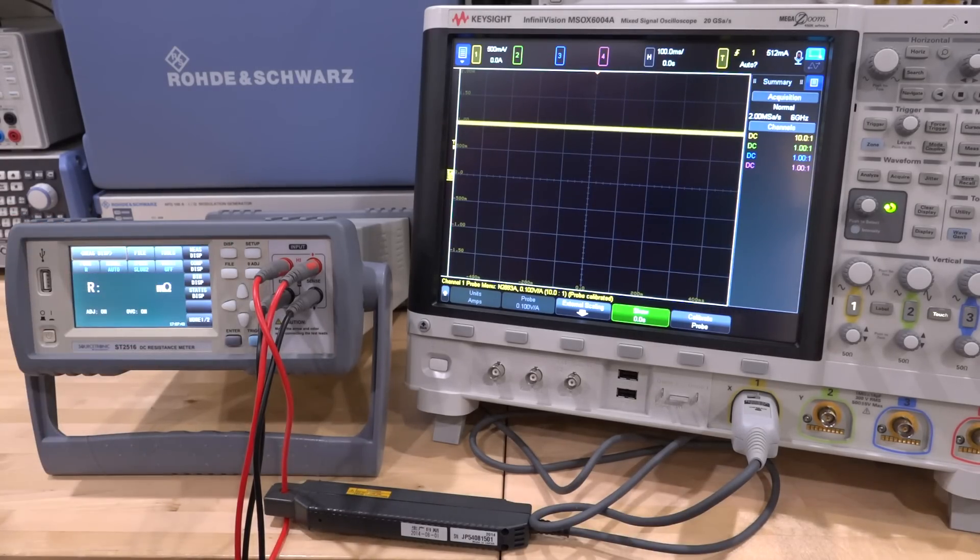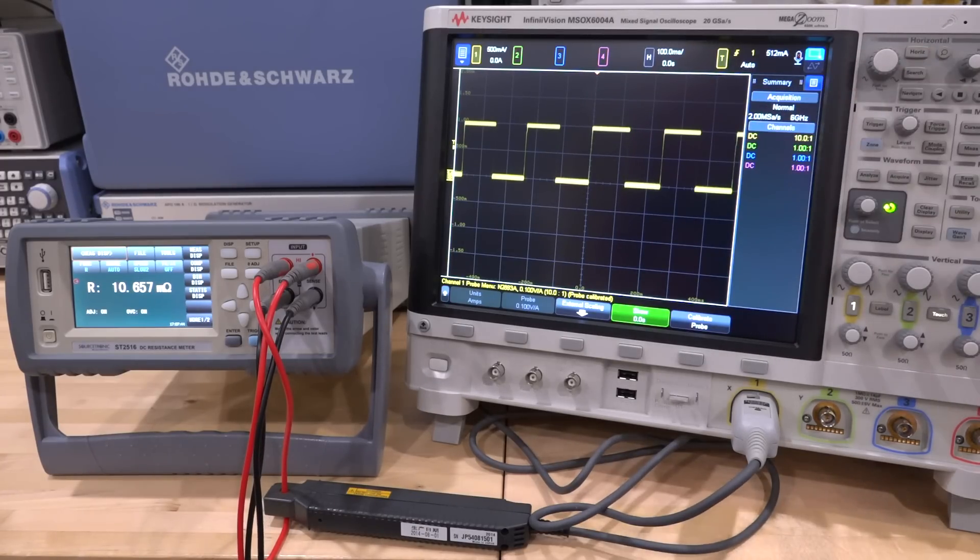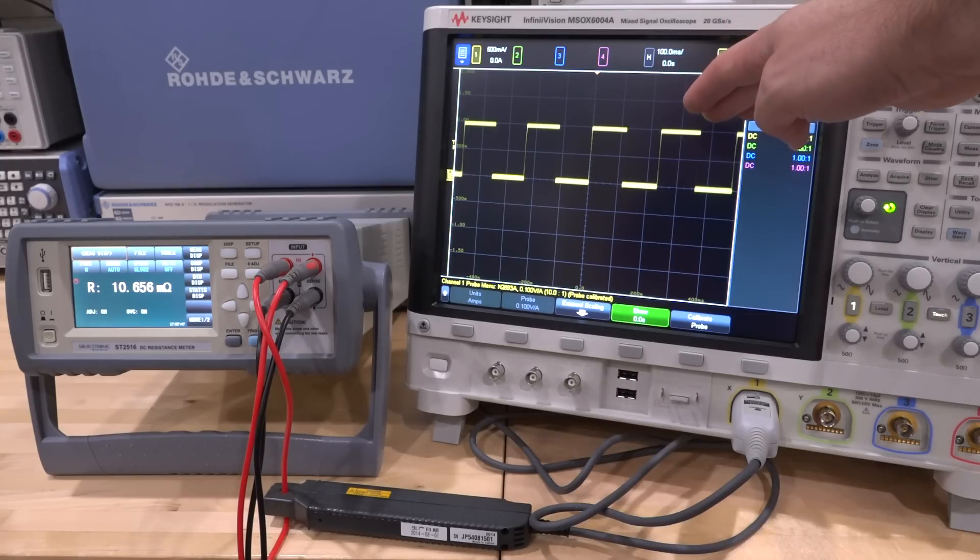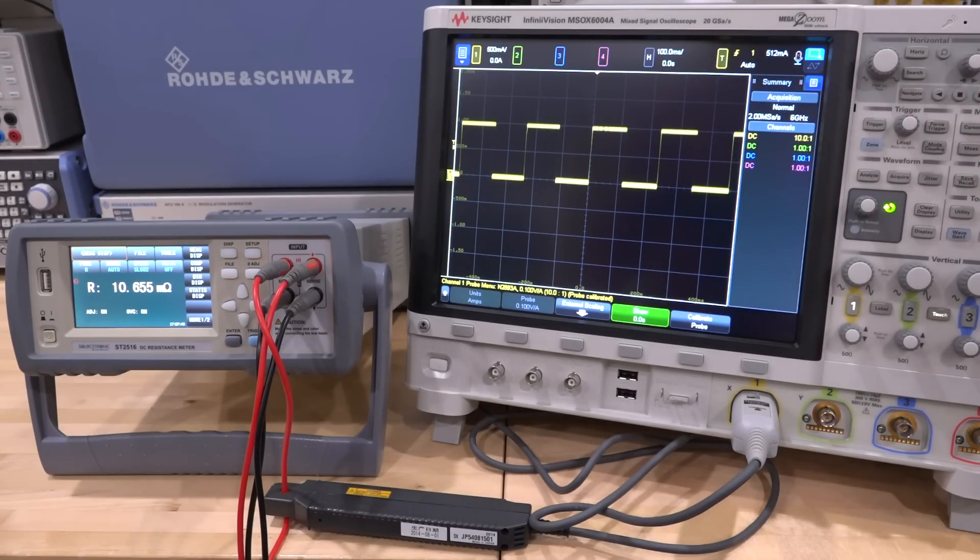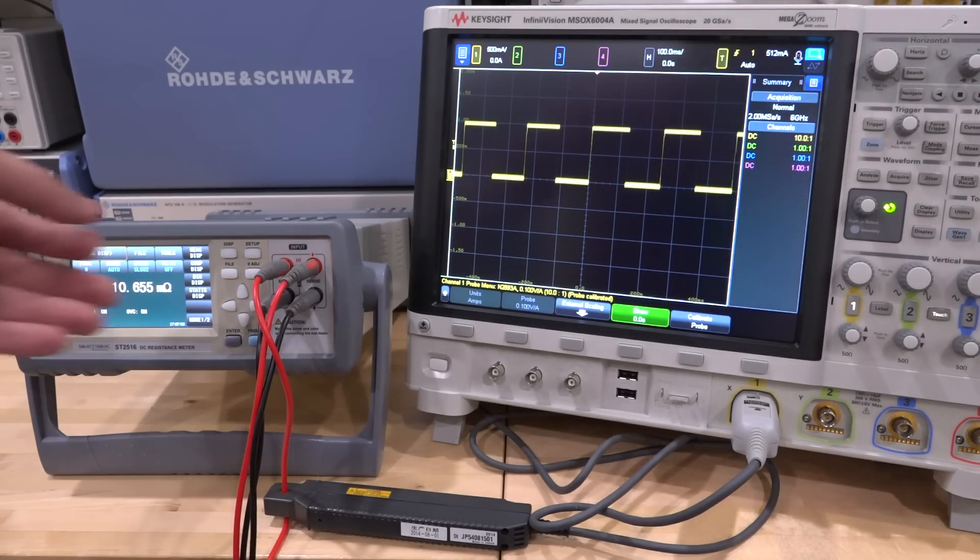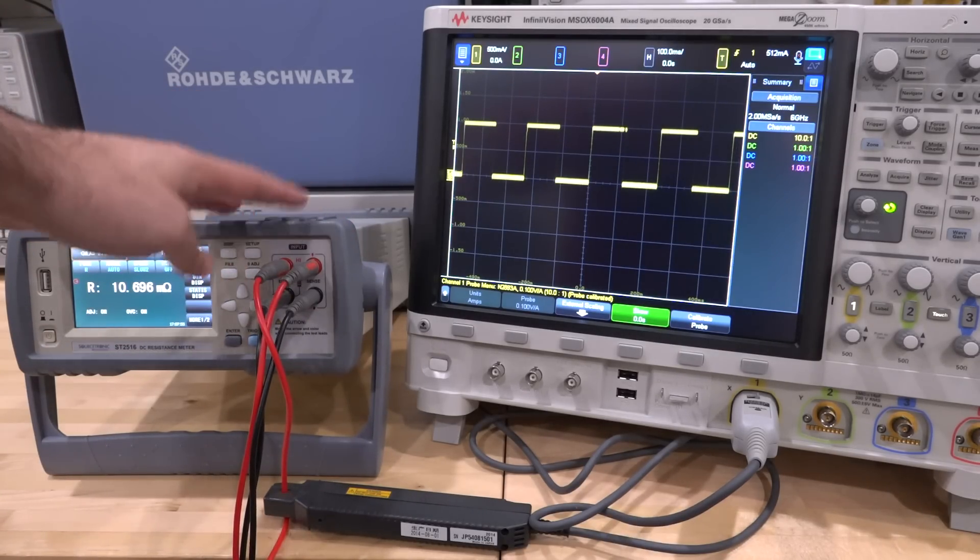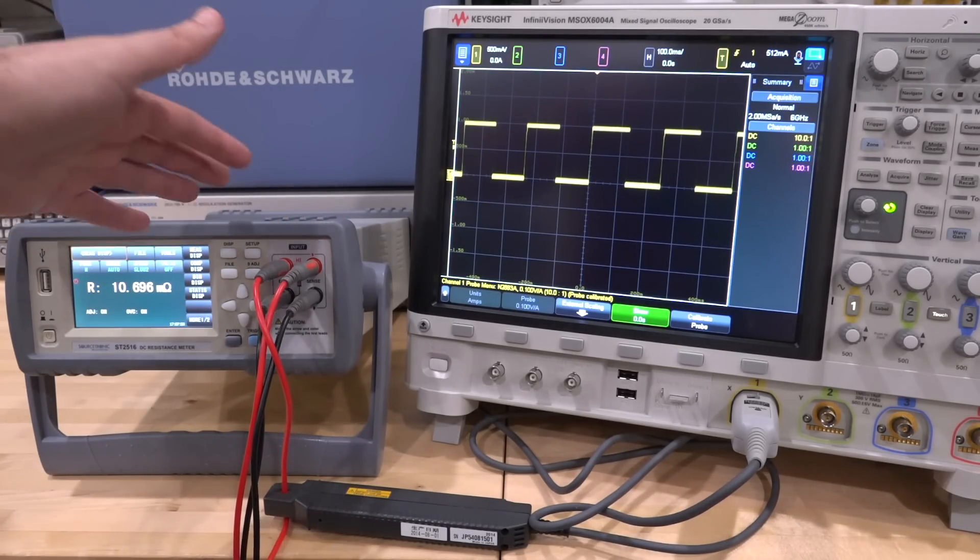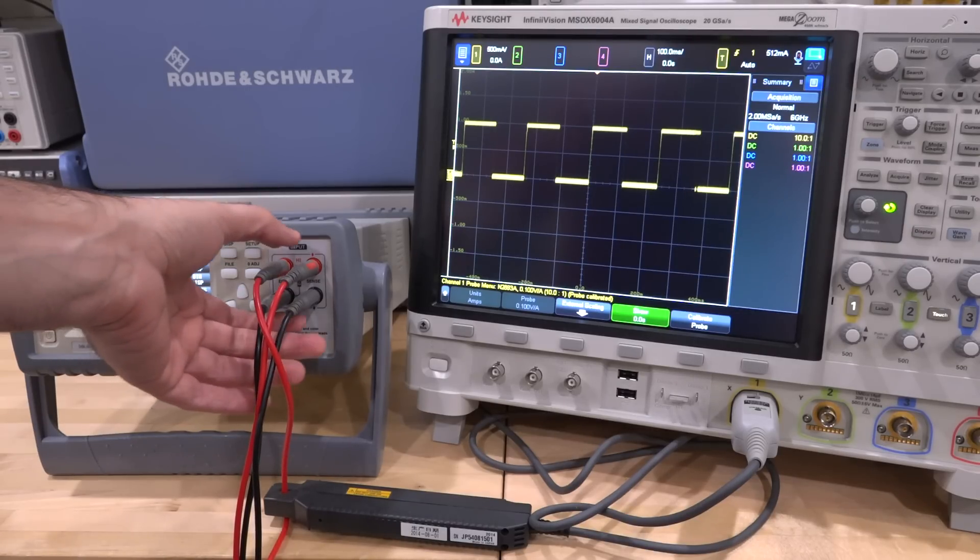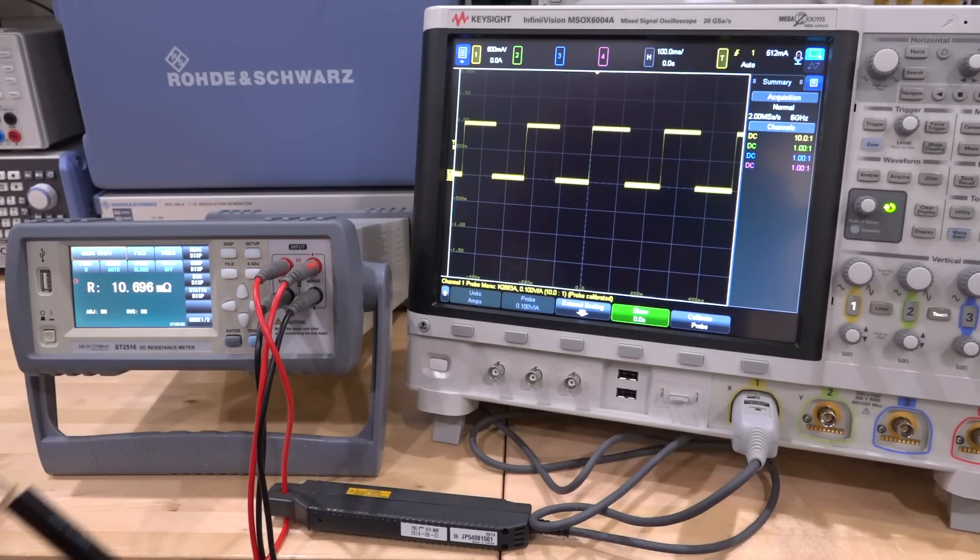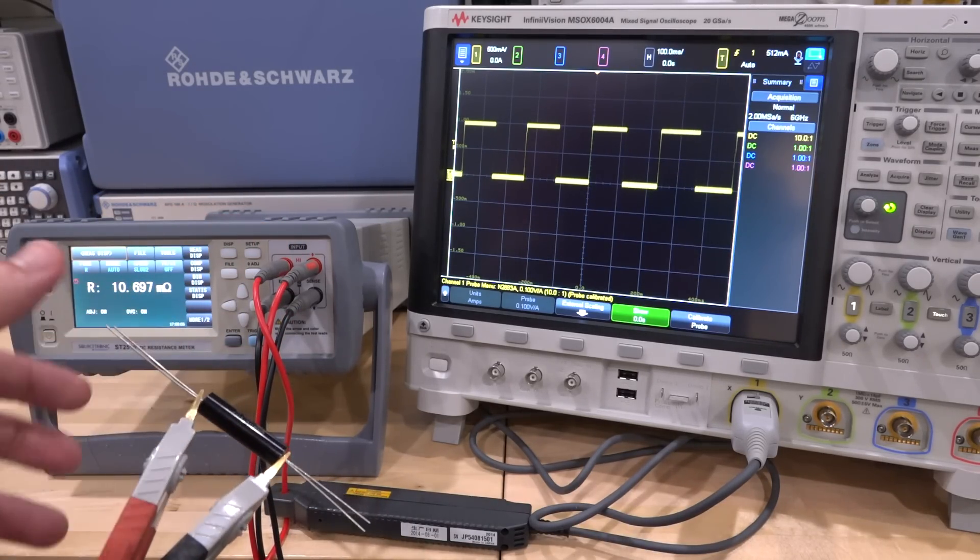We can see the value of that resistor over there but let's see what happens when I turn on the OVC. Without changing anything else, just go over here, turn the OVC on, let's see what happens now. And look at that, now we're getting a square wave instead of the continuous one amp. So the instrument applies the one amp, then it doesn't apply anything, and then one amp and then nothing and it continues doing that. Why?